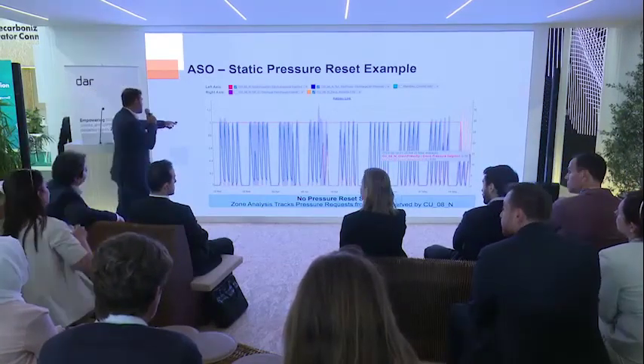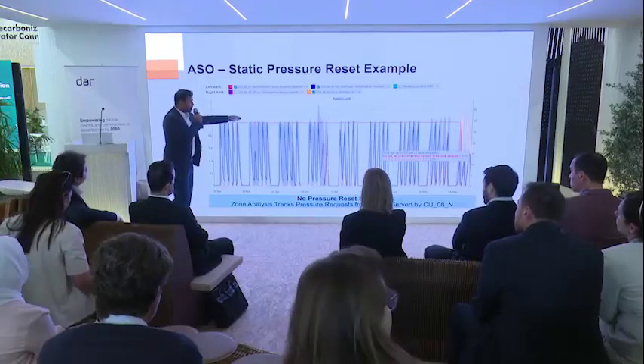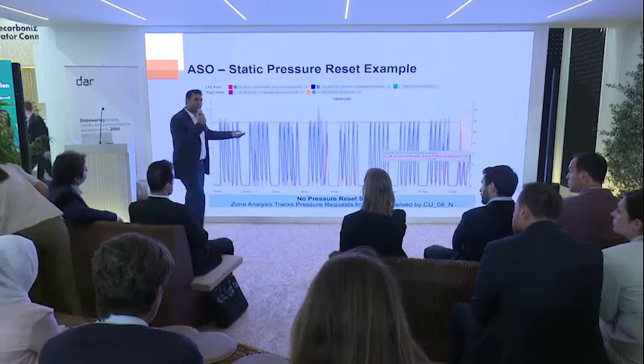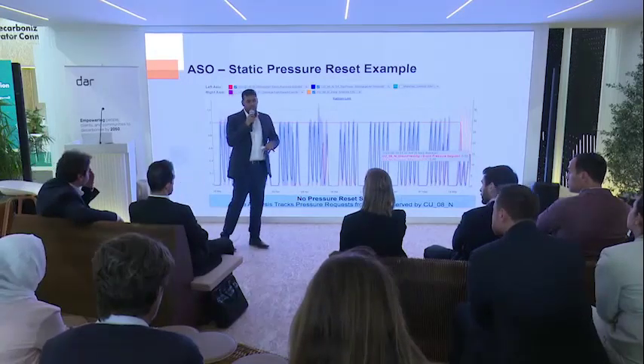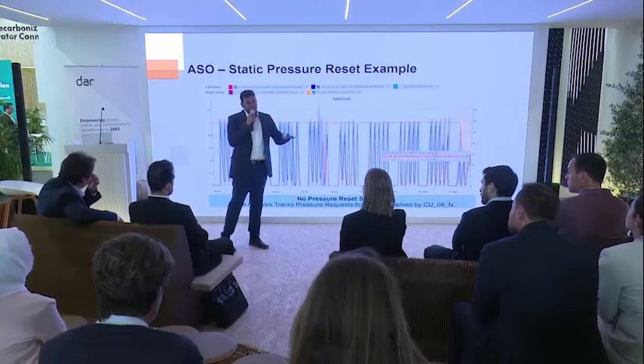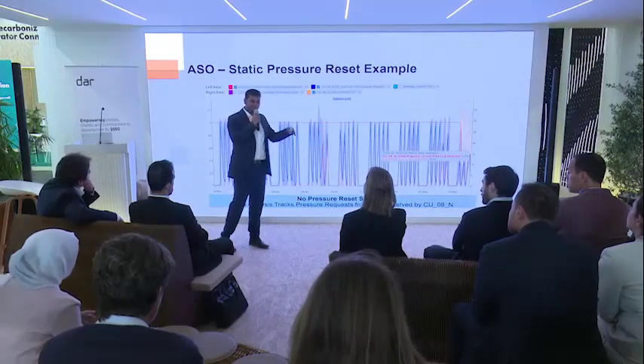So what you're looking at is a set point that is consistently reading one value. It never resets. And why is resetting important? Well, within the building, there are times when there are more people, times when there are fewer people. And based on the changes in the building, you should actually be controlling and running your equipment differently.